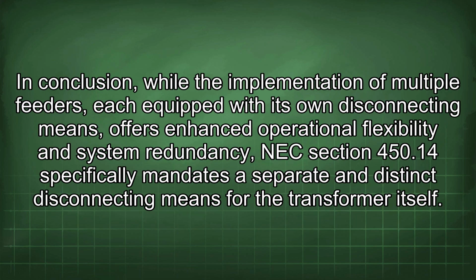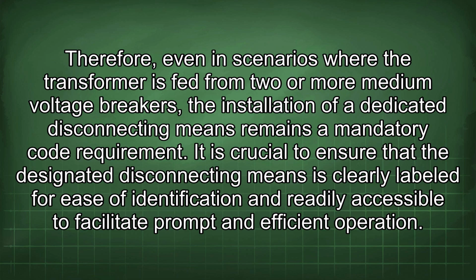In conclusion, while the implementation of multiple feeders, each equipped with its own disconnecting means, offers enhanced operational flexibility and system redundancy, NEC Section 450.14 specifically mandates a separate and distinct disconnecting means for the transformer itself. Therefore, even in scenarios where the transformer is fed from two or more medium voltage breakers, the installation of a dedicated disconnecting means remains a mandatory code requirement. It is crucial to ensure that the designated disconnecting means is clearly labeled for ease of identification and readily accessible to facilitate prompt and efficient operation.